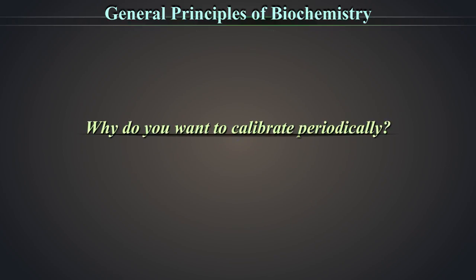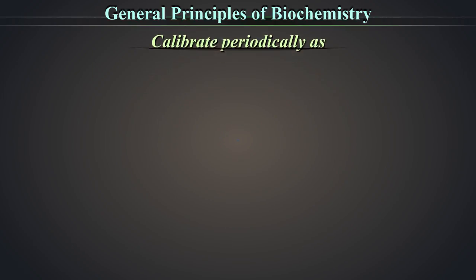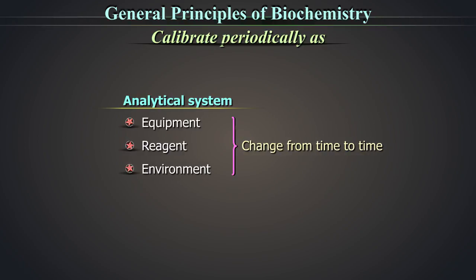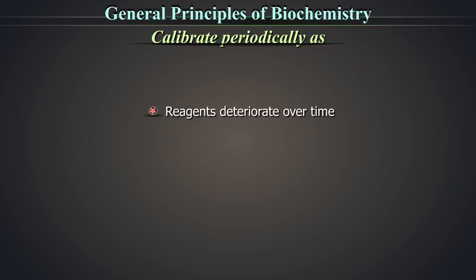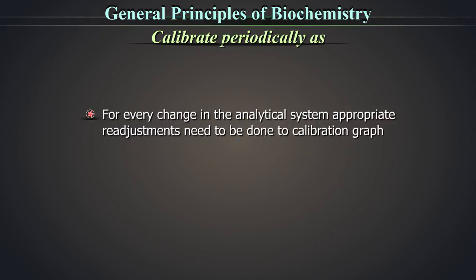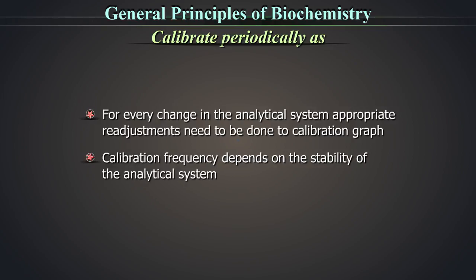Why do you want to calibrate periodically? We have to calibrate periodically as the analytical system, equipment, reagent and environment change from time to time. Reagents deteriorate over time, equipment has wear and tear, room temperature fluctuates and so on. For every change in the analytical system, appropriate readjustments need to be done to the calibration graph. So your calibration frequency depends on the stability of the analytical system.